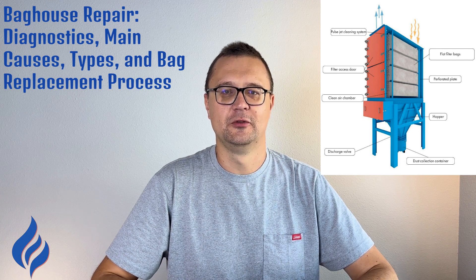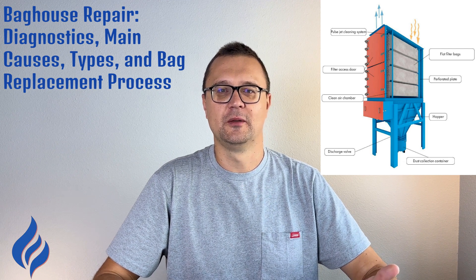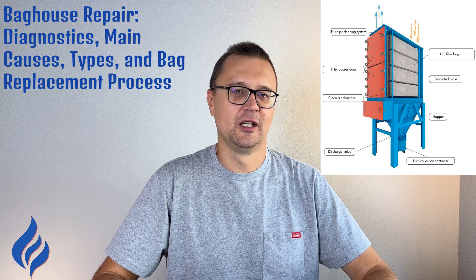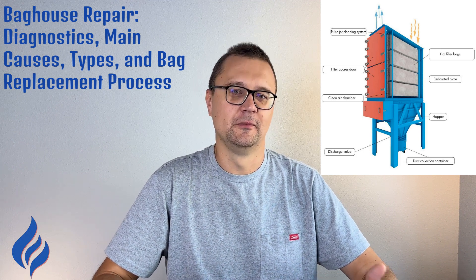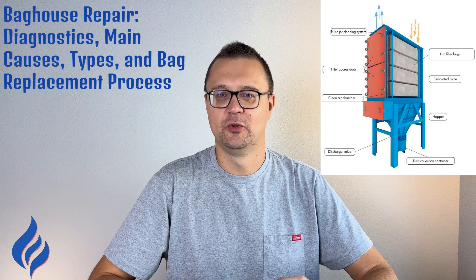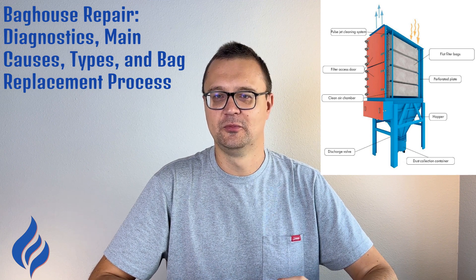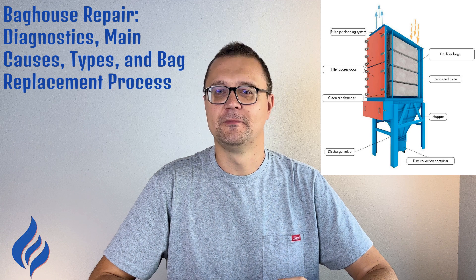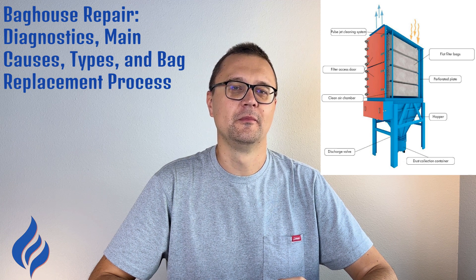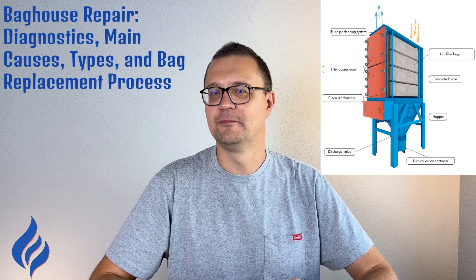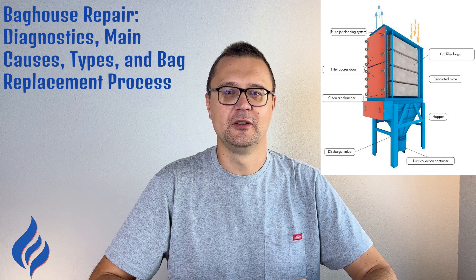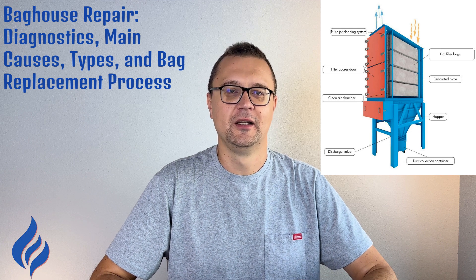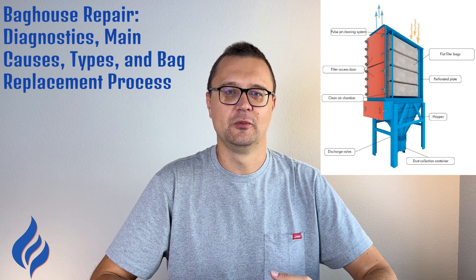Cleaning and Restoration. Dust and residue can build up inside the system over time. Thorough cleaning using vacuums, scrapers, or compressed air can restore your system's efficiency. Be sure to clean internal components like diffusers and ducts to prevent wear on the sleeves. Replacement of Seals and Gaskets. Worn seals and gaskets need to be replaced to maintain system tightness. Leaky seals can lead to contaminated air escaping and reduced system performance.